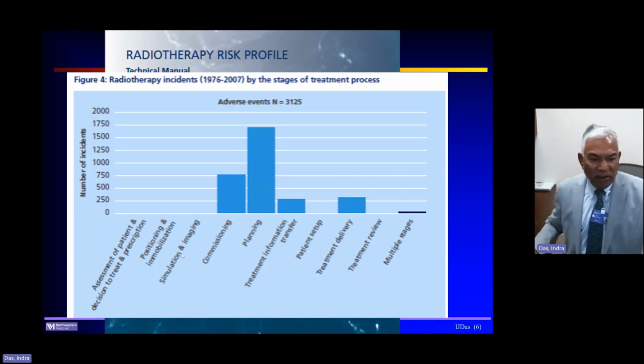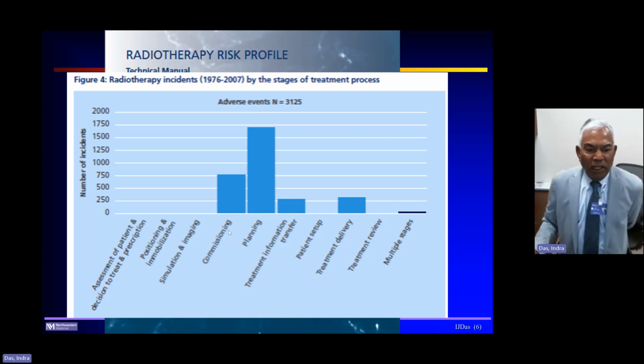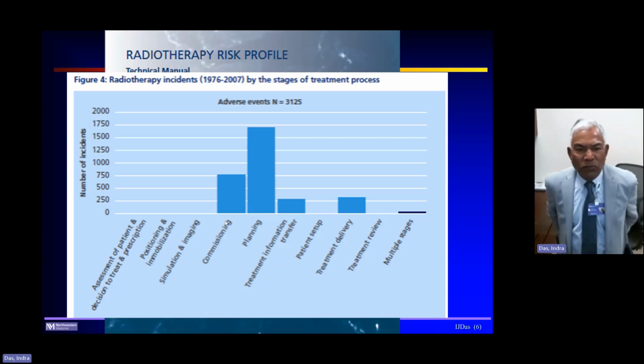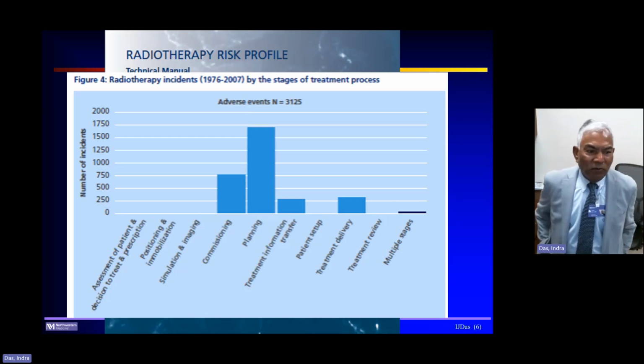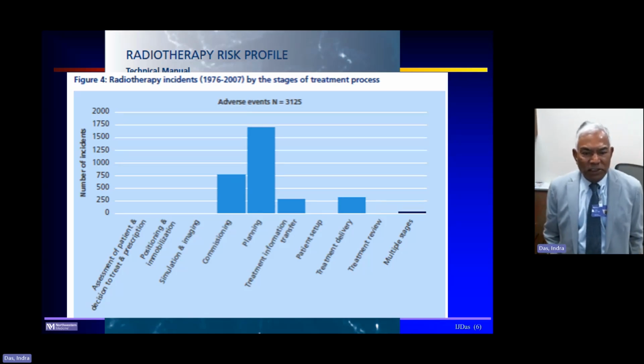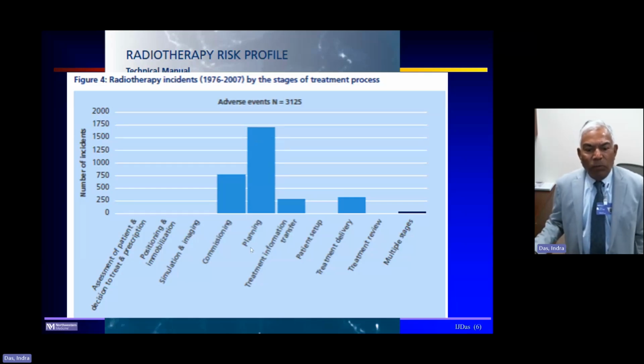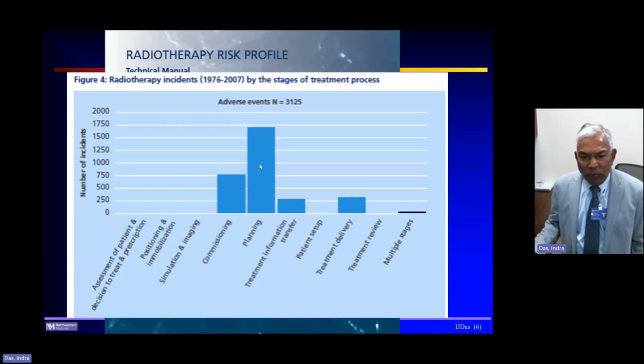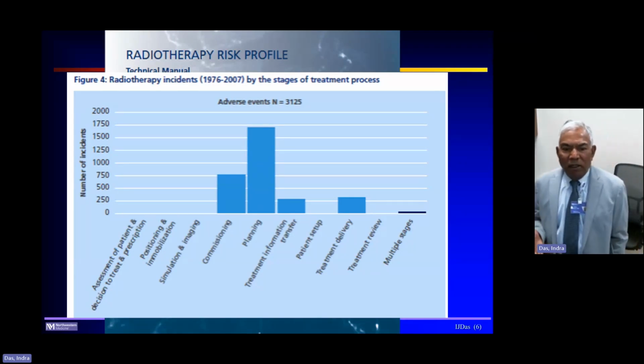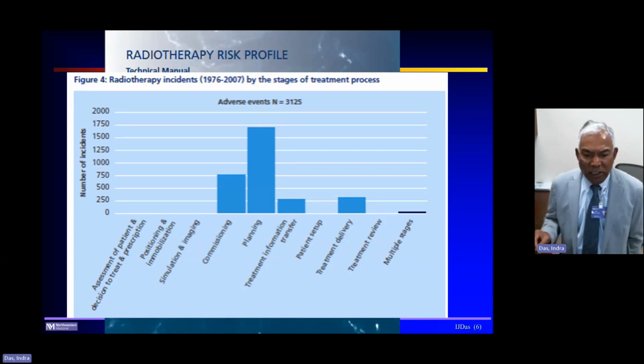And when they looked at these big errors, they divided them into various categories. But let's take where it matters. The first thing that comes to us is that the commissioning data becomes critical. And for commissioning data, you can see that there were 750 incidents where the commissioning data were either inaccurate or not okay. Then the next highest probability of errors is planning. Obviously, these days, if you have done the proper things, you do a double check, and that's a process that the dosimetrist and you manage.